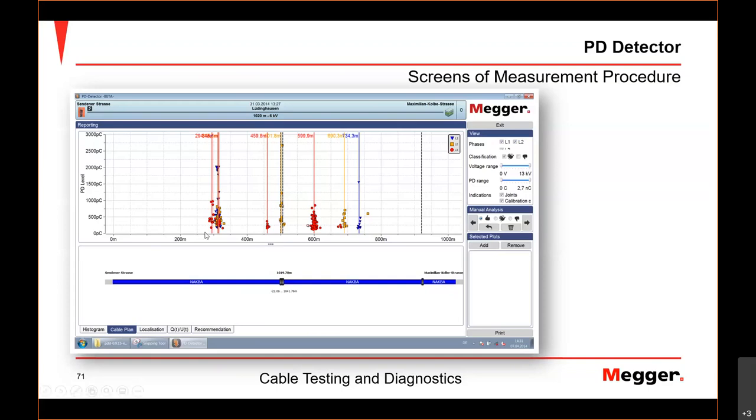Second consideration is how high are they? I mean, if they go 1,000, 3,000, that's not good. Sometimes you see some that go to 20,000 where you say, hey, this is really bad. But again, there it's a little bit experience, and you might say, well, we know where it is. We just let it run, and if it fails, we know pretty much right away which joint to exchange.